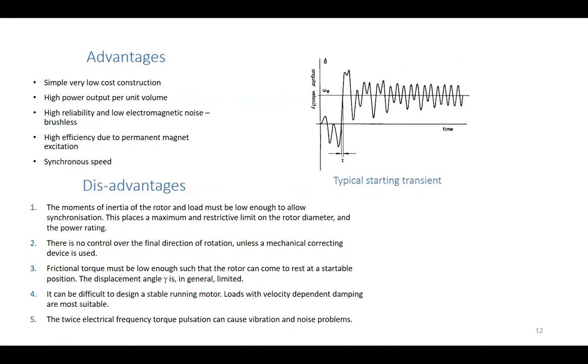So obviously, to be able to accelerate that quickly in order to synchronize, the moment of inertia of the rotor and the load must be low enough to allow that synchronization to occur. And this obviously places quite a severe restriction on the rotor diameter and the power ratings. That's why these motors are very small. And also there is no control over the final direction of rotation.